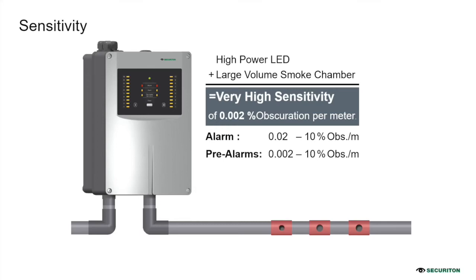Is this an independent system, or can it be connected to a fire alarm control system of Securiton or a third-party fire alarm control panel? So you can use the aspirating smoke detector as an independent system, or also connect it with any make of fire alarm system through their modules. So both are possible.